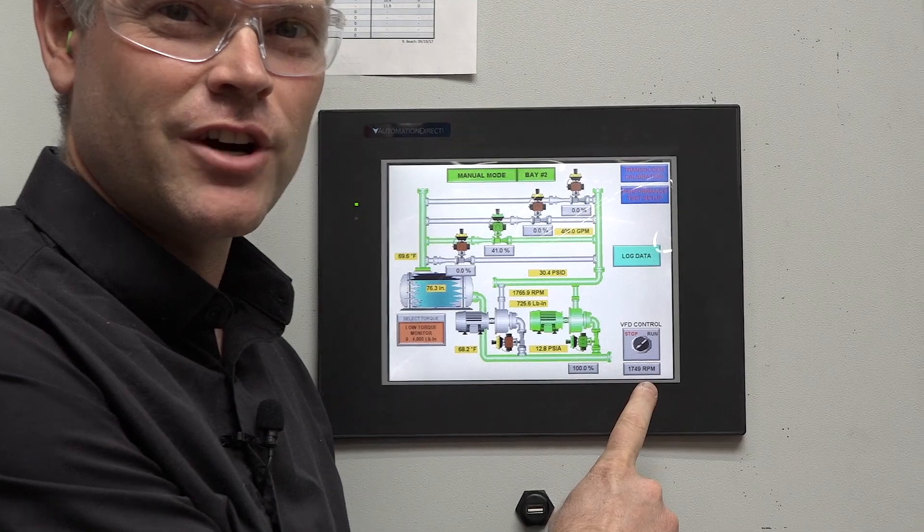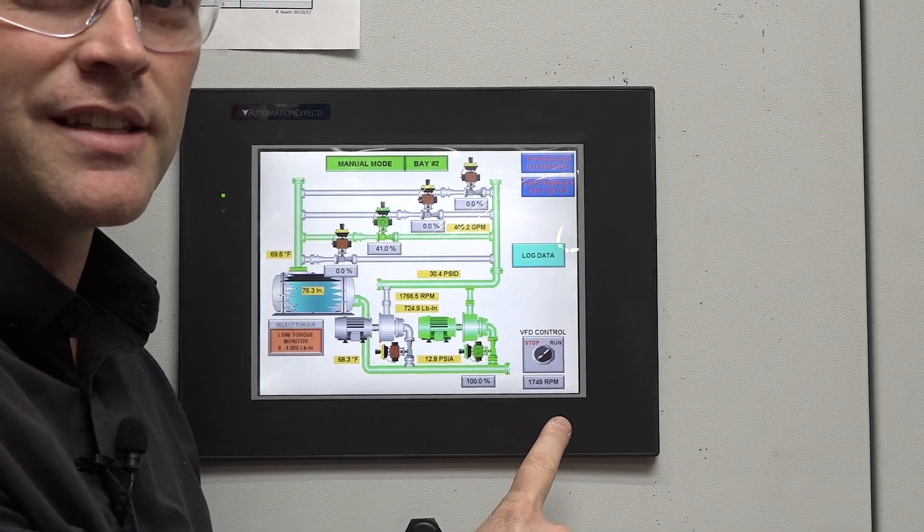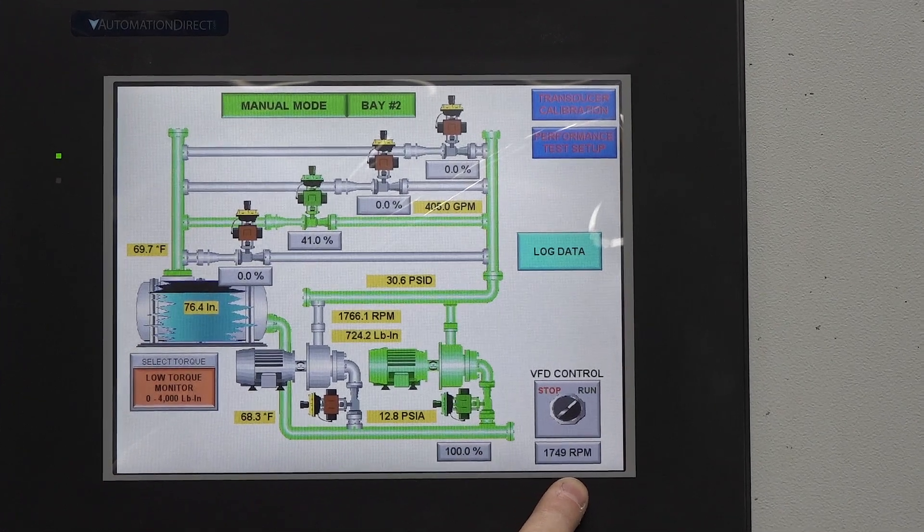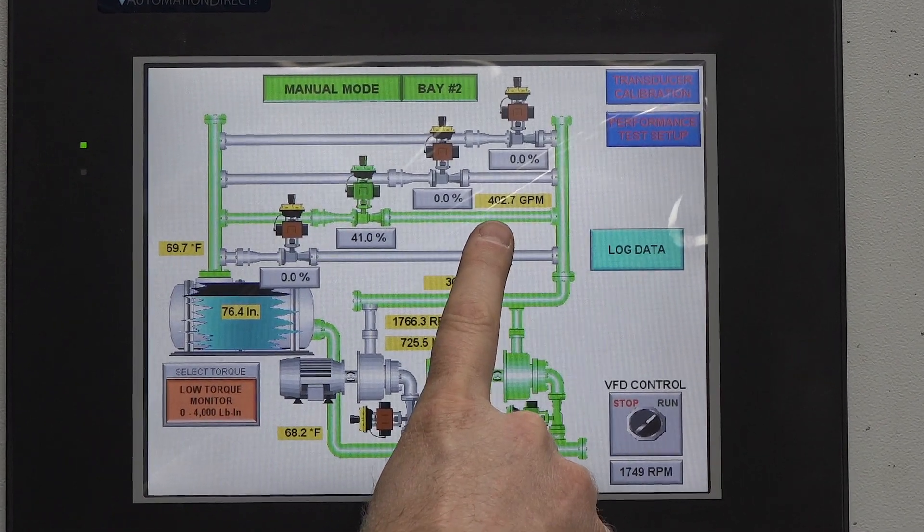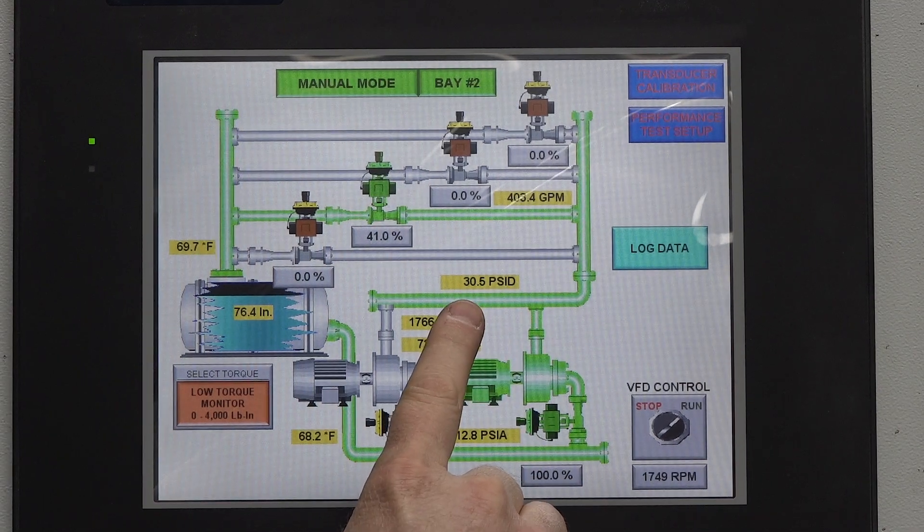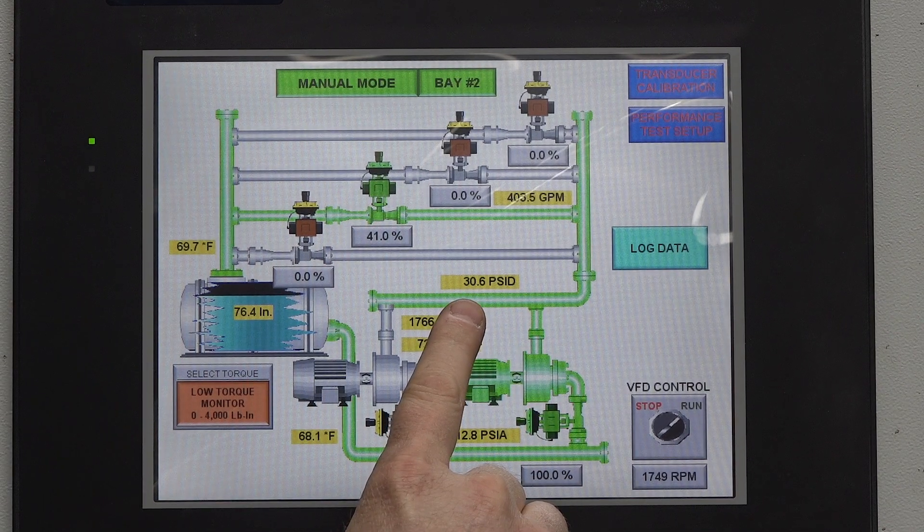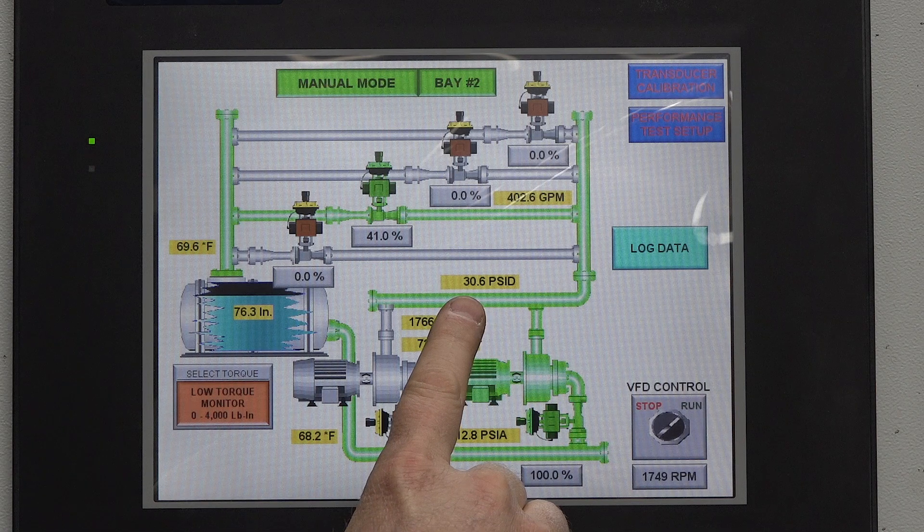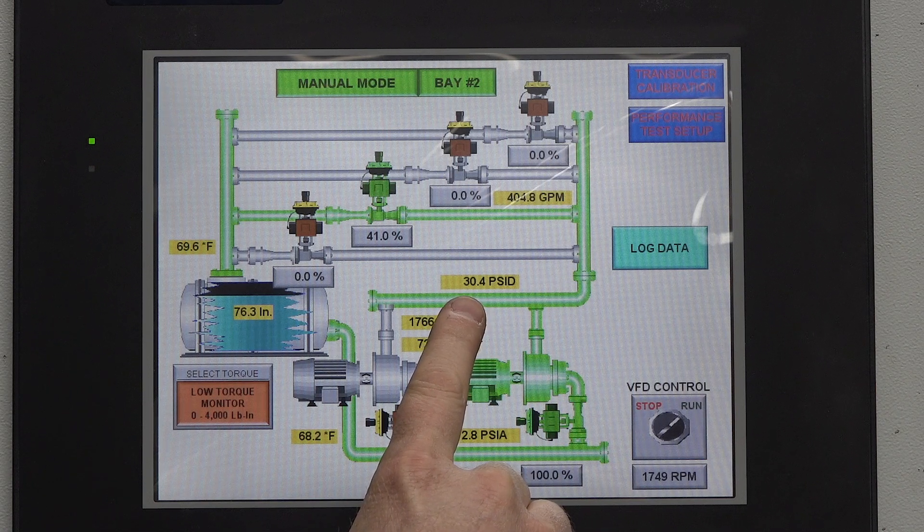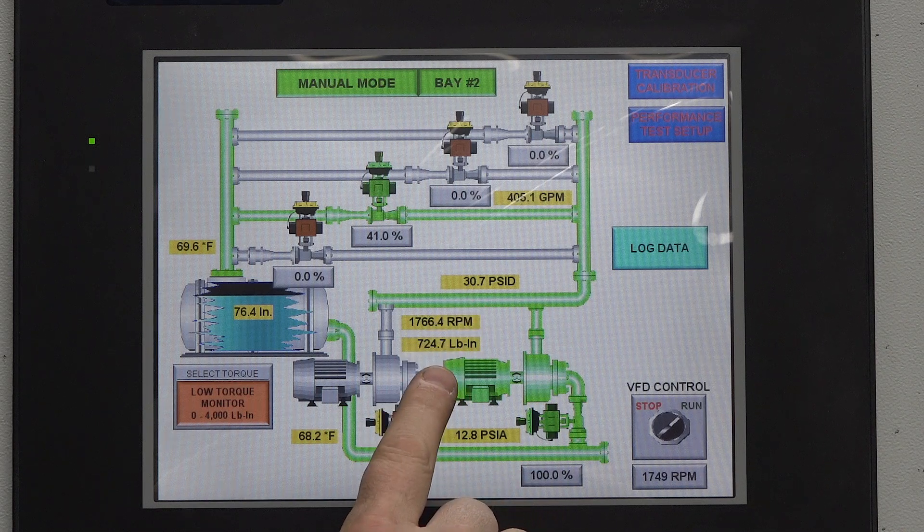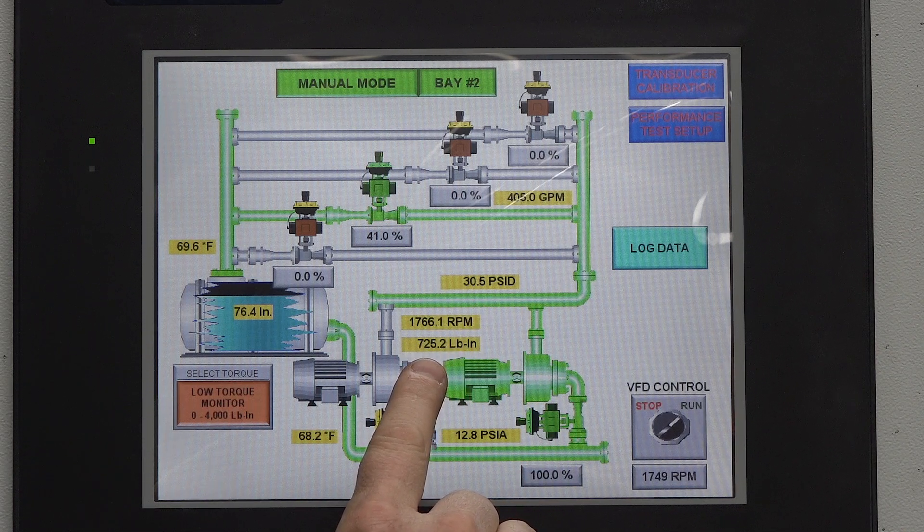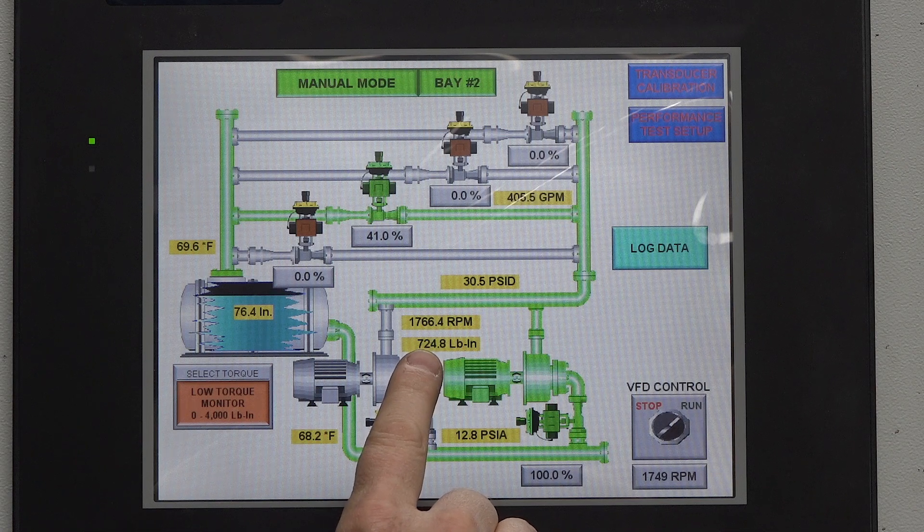For this demonstration we're going to start with the pump operating at 1750 rpm. We're capturing our flow at just around 400 gallons per minute. Our differential pressure is 30.6 psi which is equivalent to 70.6 feet of head. We're then capturing our torque which is calculated to 20.3 horsepower.